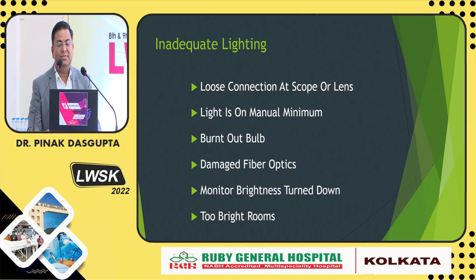Inadequate lighting is another issue. Many times, because of repeated usage, the fiber inside the light cable may fracture. So though you may have a good light source, if it's not transmitted adequately—if only 20 or 30% of light gets transmitted—in spite of having a good light source, you won't have proper vision.